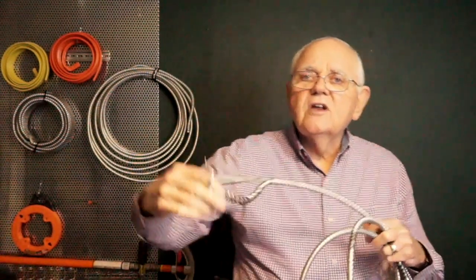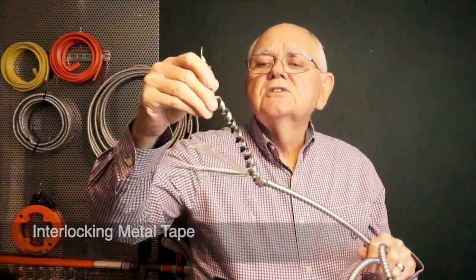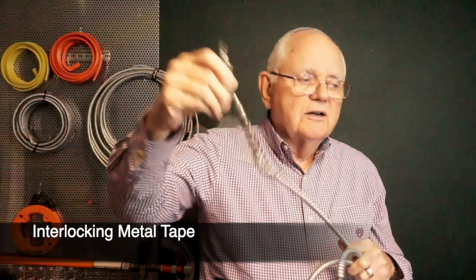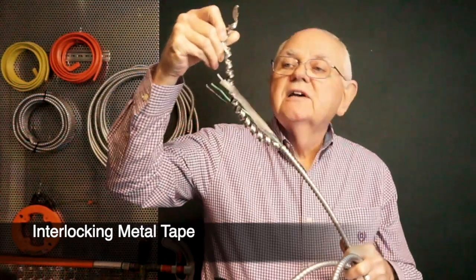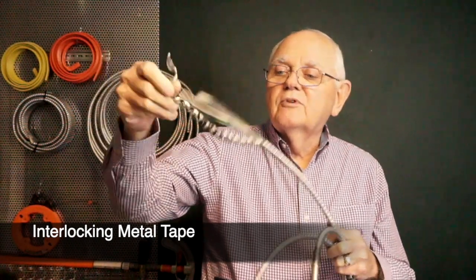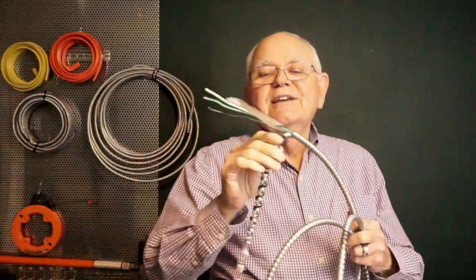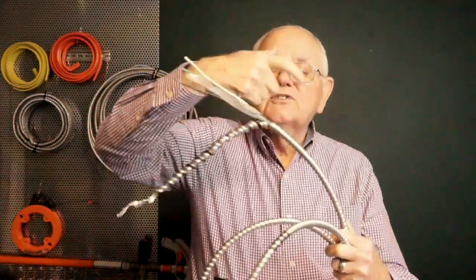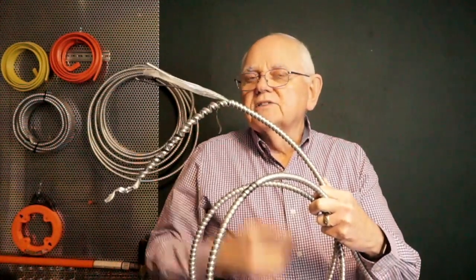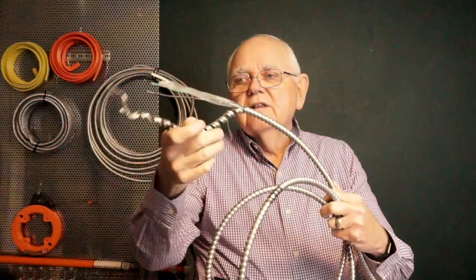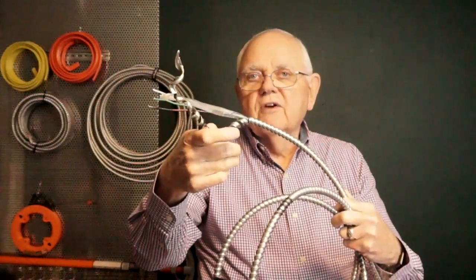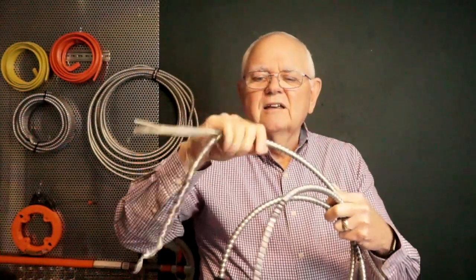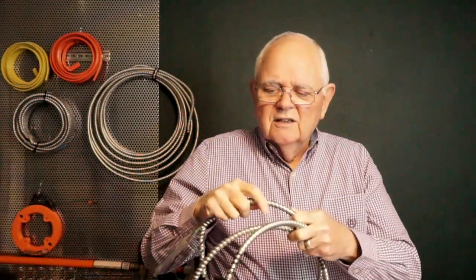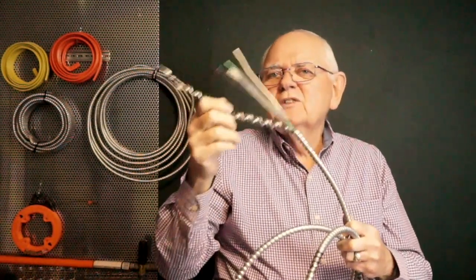What I have here is an interlocking metal tape type of construction. So this is, and I just kind of pulled it apart. And if you've worked with MC cable, you know how this is. It just stretches on out, you pull it and pull it. And then, of course, you cut this off and throw it away and terminate your cable. But anyway, this is just some metal tape, and it's wrapped around on top of each other so that it's what it looks like right here, interlocking metal tape. Now, one thing, if you think about it, just getting a little ahead of ourselves here, but look at that. Do you think that's going to make a good equipment grounding conductor? Oh, maybe not, huh? If I bend it too far, I can break it and pull it apart. So probably not going to want to use this as the equipment grounding conductor.